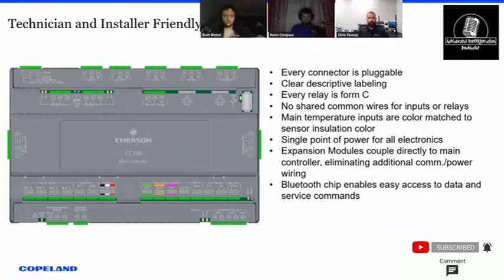Another little nice to have is there are no shared common wires for inputs or relays. And that goes across the Form C relays and across the inputs on the bottom. And really what that does for you, it's just a small nice to have on the electrical tray. When you have shared commons on all those sensor wires, you tend to get manufacturers that'll have to put splicing connectors in there and bunch all the commons up and bring one common wire back to a terminal somewhere, versus everything's individual commons, very clean on where everything goes for each sensor.